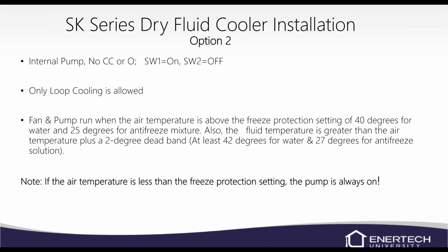Option 2, this will be switch 1 on, switch 2 off. This will be only loop cooling is allowed. So the fan and the pump are going to run when the air temperature is above the freeze protection setting of 40 degrees or 25, depending on your dip switch.